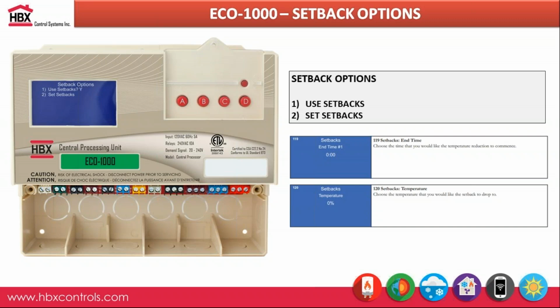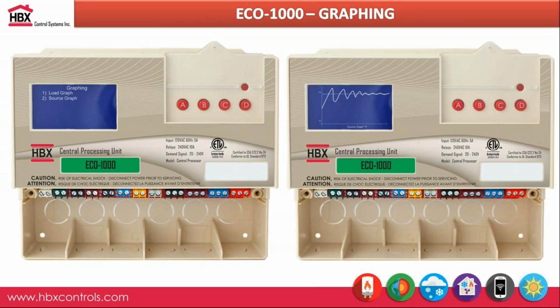So this is kind of like your temperature scheduling in terms of a residential or commercial space. Maybe you don't want to have it as hot during the weekend just because no one's at the office. So you can actually change your design temperatures based off those setback options. It's a nice feature to have, especially for those commercial spaces where typically a lot of people aren't there on those weekends.